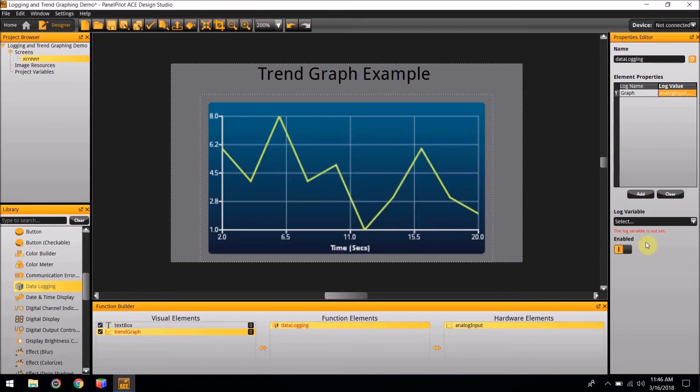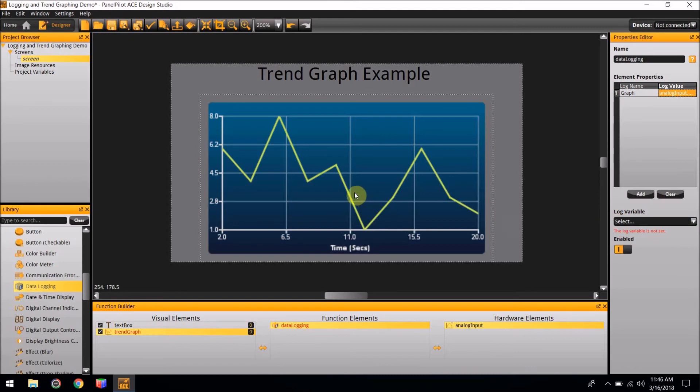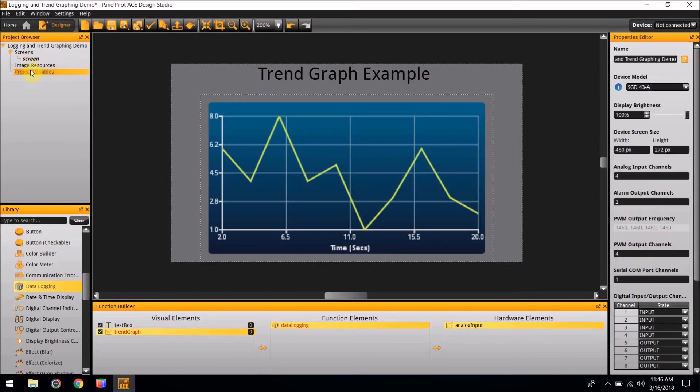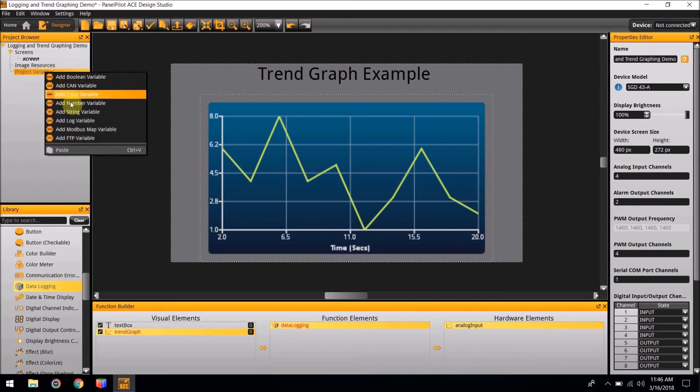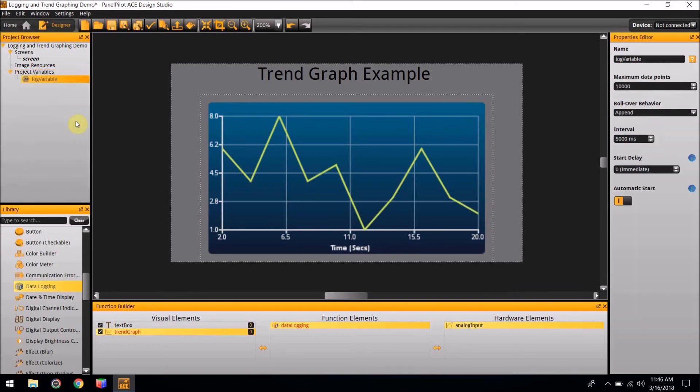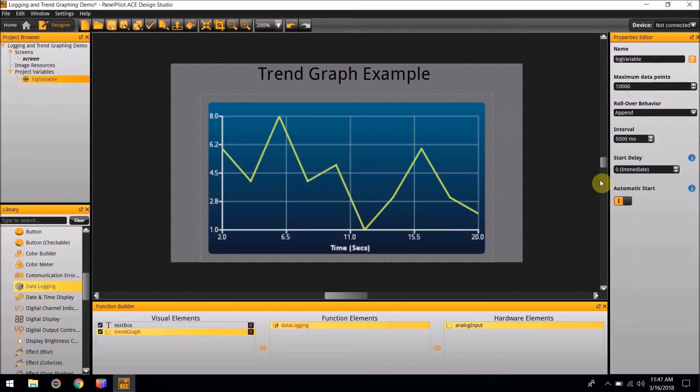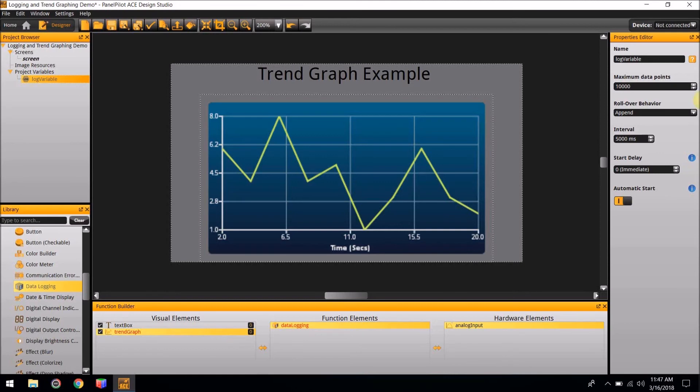Next, in the same Properties Editor, at the bottom of the screen is a log variable that will need to be tied to the Trend Graph also. To add a log variable, in the Project Browser to the left of the screen, there is a Project Variables section. Right-click on the Project Variables and add the Log Variable. In the Log Variables Property Editor, you can change how many data points you would like to be collected, if you would like them to roll over, interval, and if you would like a start delay. For this project, we would like the interval to be every 3 seconds. So make the interval 3000 milliseconds.